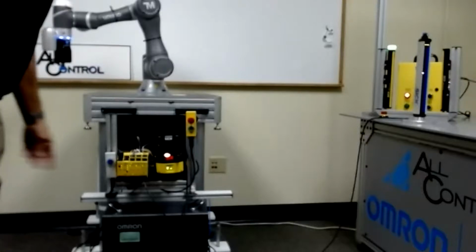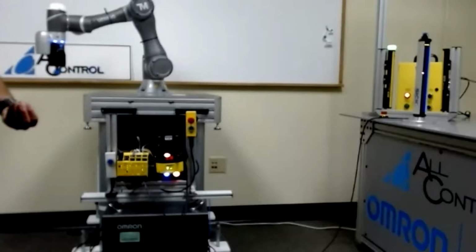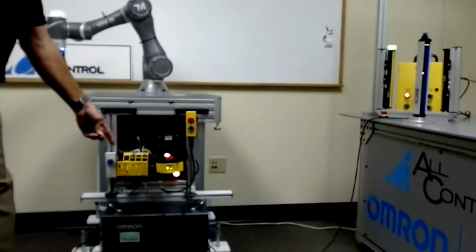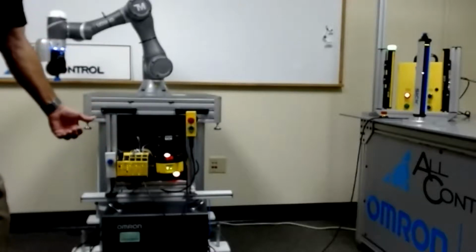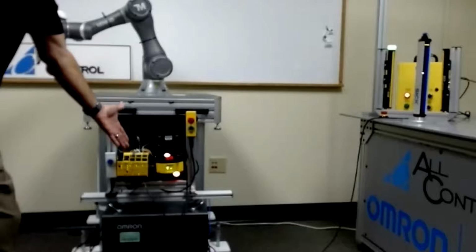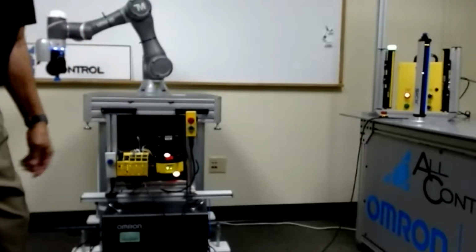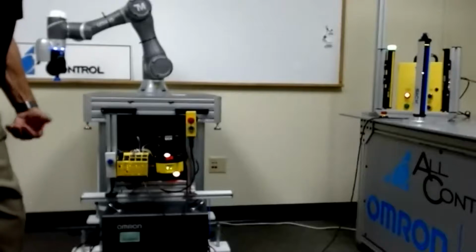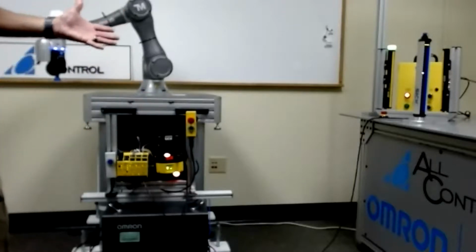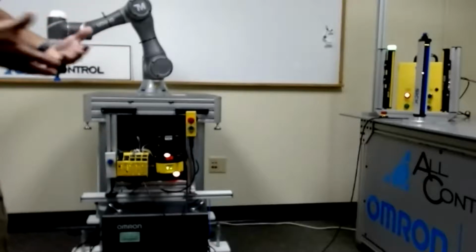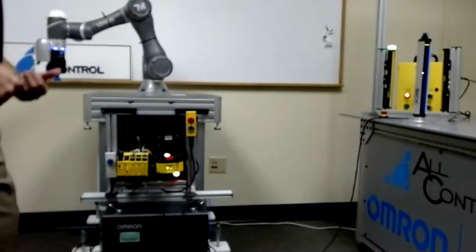This is your CPU, and this is the cloning module. One thing nice about these is they have the cloning modules built in. So you never have to reprogram after you've done your initial setup. So I dump the program that we already provide for you into the controller. I dump the program into the laser scanner. This is over EtherNet/IP safety. When I did this one, it automatically configured all of your Ethernet assemblies and everything for me. So it was very simple.